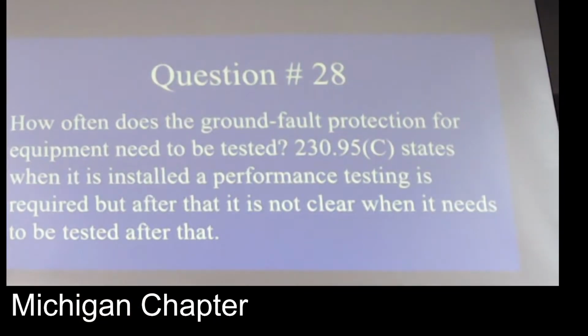Tim, question 28. How often does the ground fault protection for equipment need to be tested? 230.95(C) states that when it is installed, a performance test is required, but after that, it's not clear when it needs to be tested again.